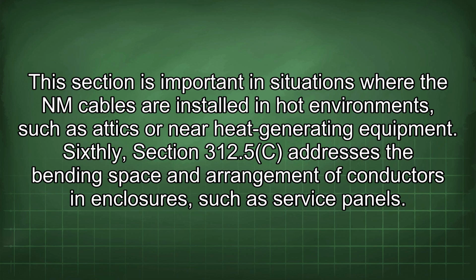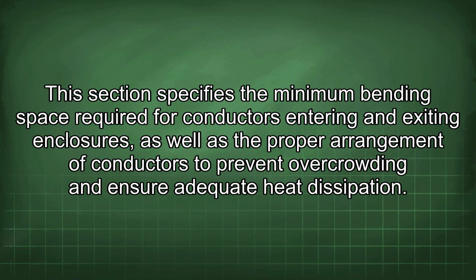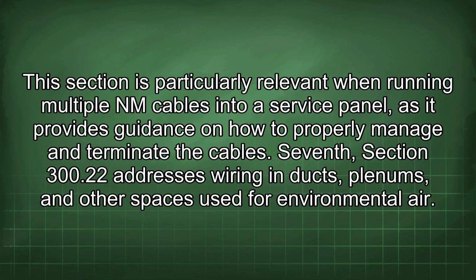Sixthly, Section 312.5(c) addresses the bending space and arrangement of conductors and enclosures, such as service panels. This section specifies the minimum bending space required for conductors entering and exiting enclosures, as well as the proper arrangement of conductors to prevent overcrowding and ensure adequate heat dissipation. This section is particularly relevant when running multiple NM cables into a service panel, as it provides guidance on how to properly manage and terminate the cables.